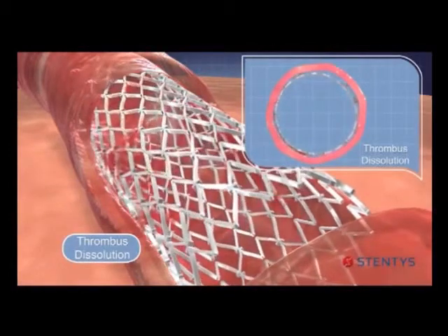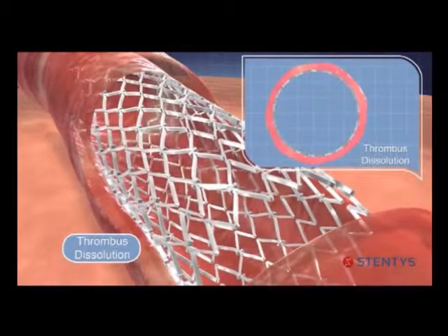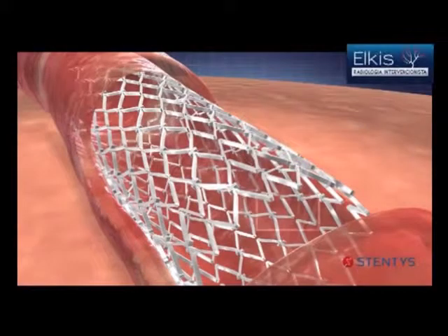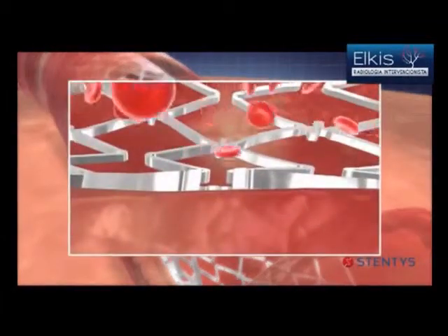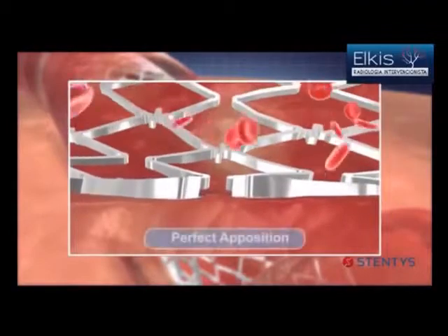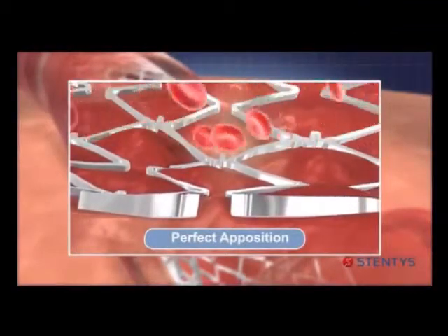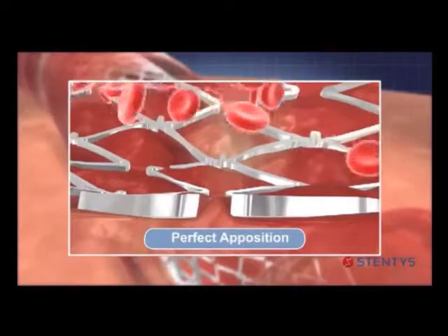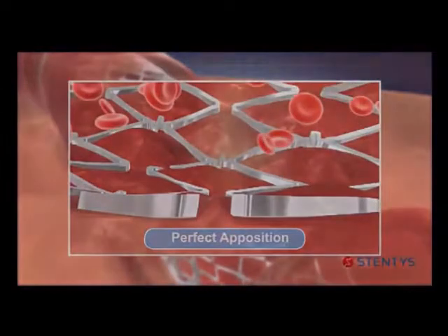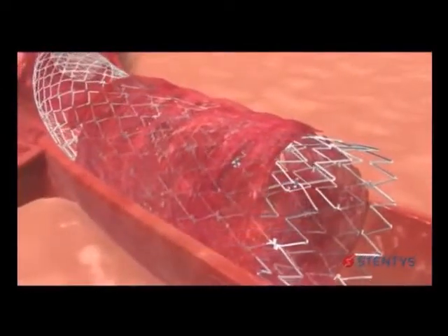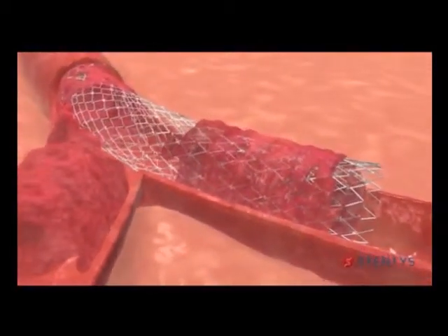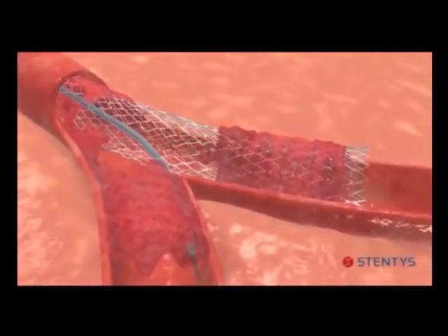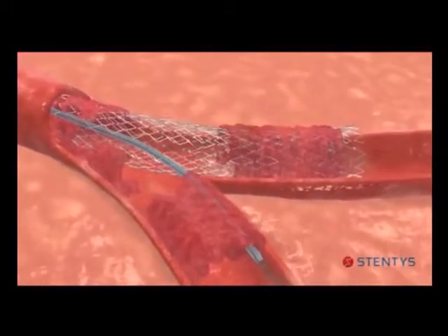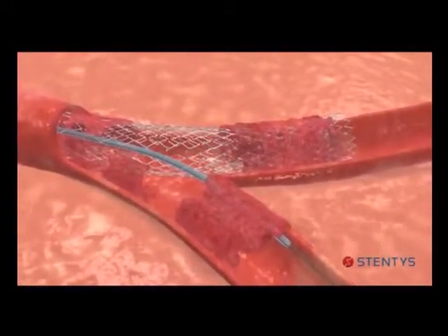Finally, as the thrombus dissolves, the stent expands further to absorb the gap left by the dissolving thrombus, thus maintaining perfect apposition throughout the remodeling process of the vessel. If the Stentys stent is deployed across a significant side branch, and if access or treatment of the side branch is desired, a guide wire and a balloon are advanced through the stent mesh and into the ostium of the side branch, as would be done with a conventional stent.